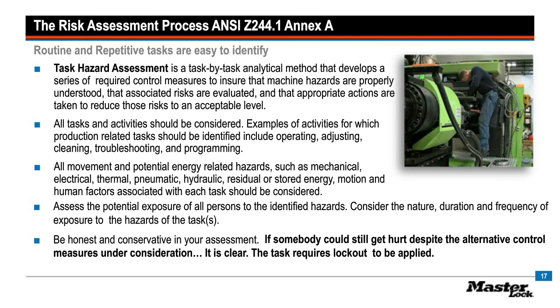Although a third of this standard has been devoted towards expanding the practice and understanding of alternative methods, we want to come back to this point. Be honest and conservative. If your alternative method is rationalizing an activity without coming up with the conclusion that we can properly control risk, it is absolutely clear the task cannot be done under power.